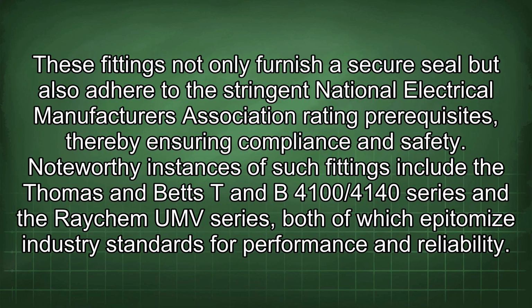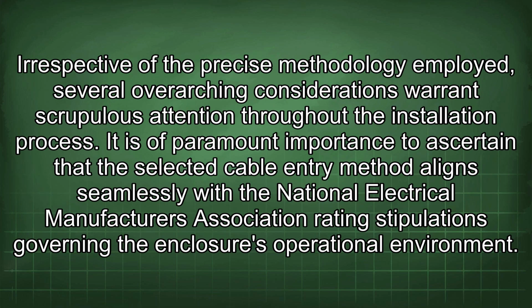These fittings not only furnish a secure seal, but also adhere to the stringent National Electrical Manufacturers Association rating prerequisites, thereby ensuring compliance and safety. Noteworthy instances of such fittings include the Thomas & Betts T&B 4100/4140 series and the Raychem UMV series, both of which epitomize industry standards for performance and reliability. Irrespective of the precise methodology employed, several overarching considerations warrant scrupulous attention throughout the installation process.